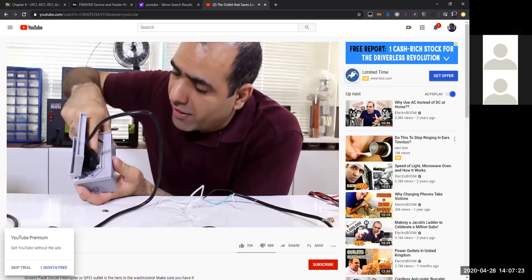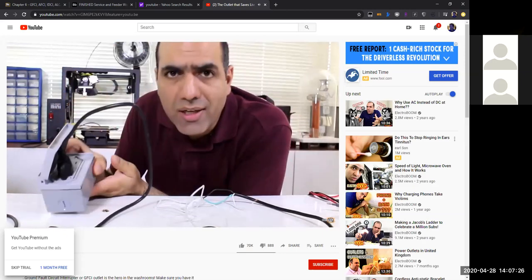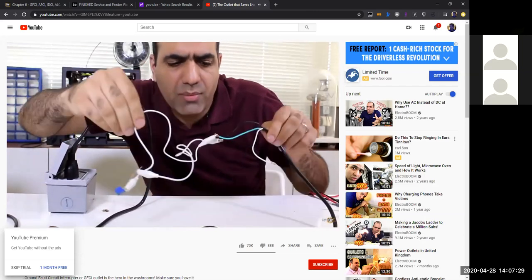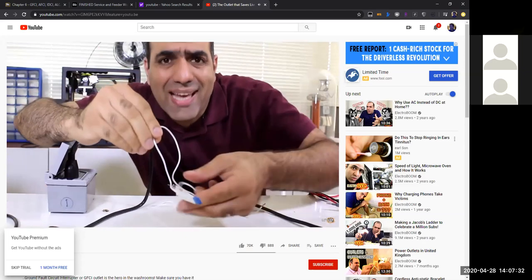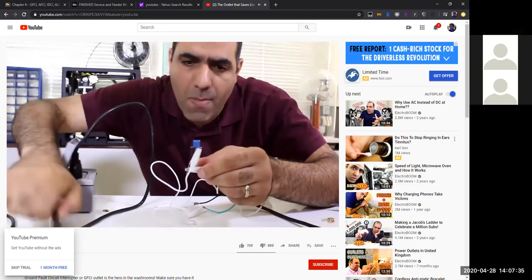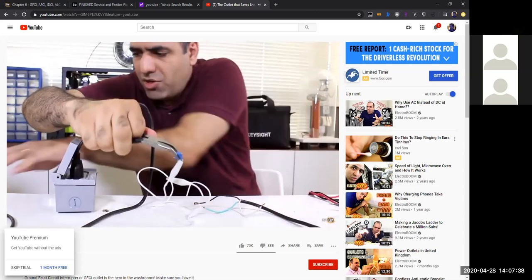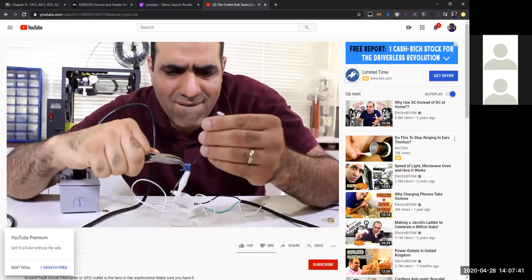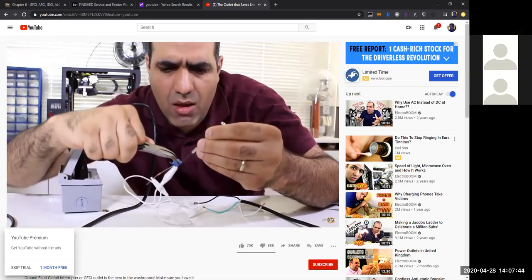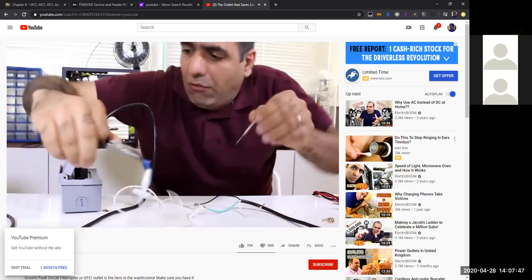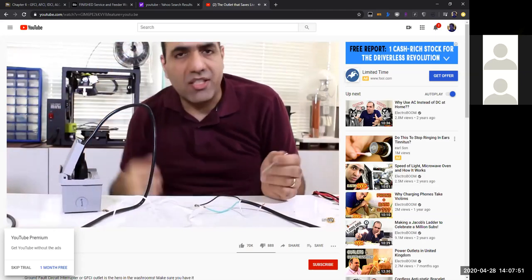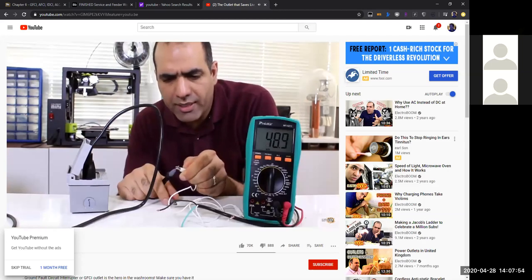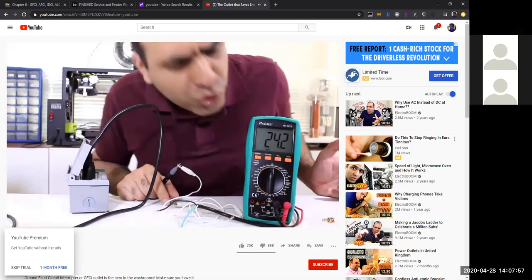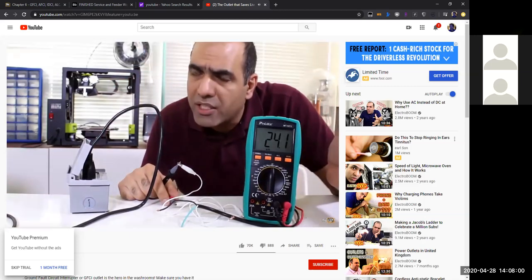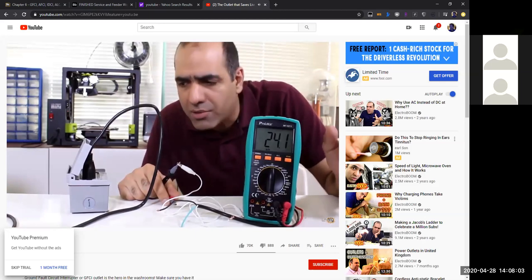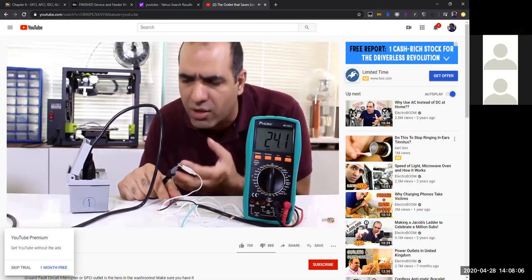Okay, I bought this GFCI outlet so I can try it outside the washroom. I connected a potentiometer between the live and earth to see exactly where it will trigger. We don't short anything. High voltage makes me nervous. Let's check the potentiometer resistance, pretty much 24 kilo ohms, which means 120 volt AC divided by 24 kilo ohms is exactly 5 milliamps. So these things are designed to trip at fault currents of over 5 milliamps.